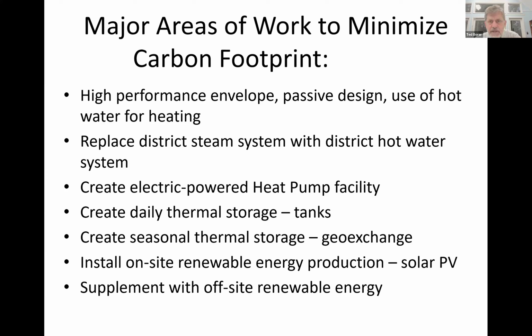We're going to replace the district steam system with district hot water. In really simple terms, you can understand why that's more efficient: brand new versus brand new, steam at 450 degrees Fahrenheit will lose a lot more heat to the ground than hot water, which might be 120 degrees. As we get closer to ground temperature, there's simply less heat loss, even if both are brand new and well insulated. But the technology of even the insulation is very different from 150 years ago versus today, where it's directly buried and there's no way for the insulation to fall off.